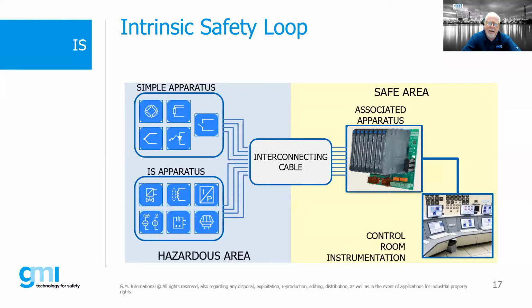We could have simple apparatus. A simple apparatus is a non-energy storing device - normal things like switches, that is not energy storing. An RTD could be a simple device. However, there are devices that will actually be powered, say like a transmitter or potentially a solenoid valve or something like that. That is considered to be an IS apparatus, a non-simple device.